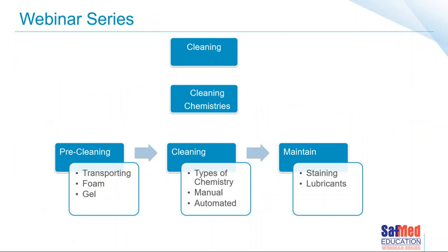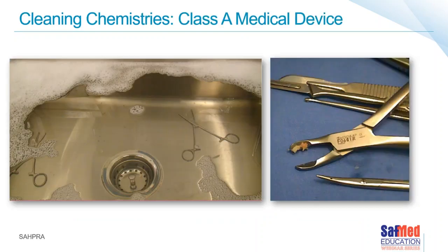So we've looked at cleaning as a principle, and now let's start to unpack the terminology and some of the concepts around the cleaning chemistries themselves. Cleaning chemistries in South Africa are defined as a medical device — in fact, all over the world, in Europe and in America, cleaning chemistries are medical devices. So remember, when we're cleaning our medical devices and our surgical instruments, we need to be cleaning them with medical device type products, not with household cleaning products. Very important point to note.